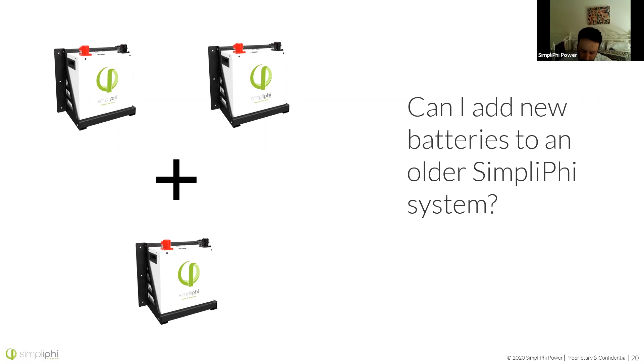Can I add new batteries to an older SimpliPhi system? The answer is yes, you actually can. One of the greatest benefits of our batteries is the ability to add new batteries to an old system. I typically stick within a 3-year recommendation, meaning that if it's over 3 years, I'd tread lightly as far as adding new batteries in, since there might be balance issues.